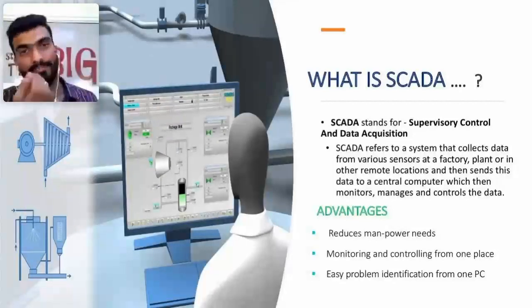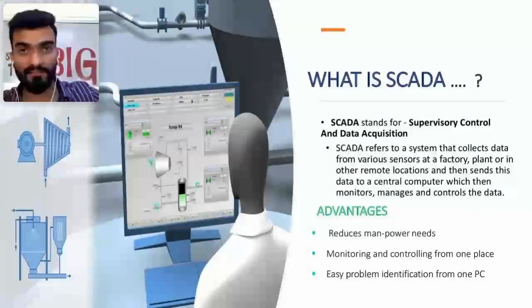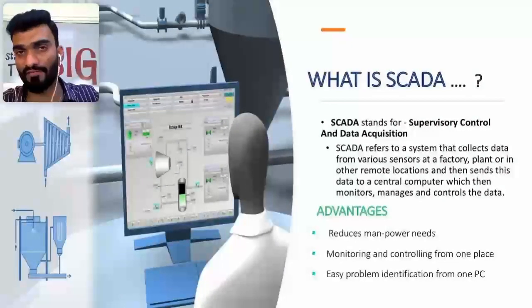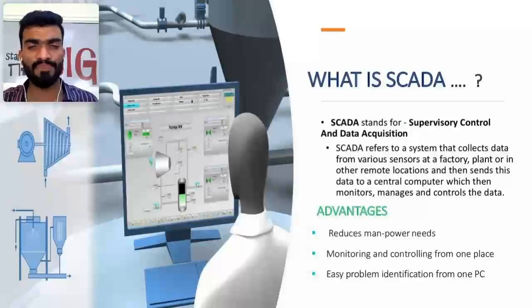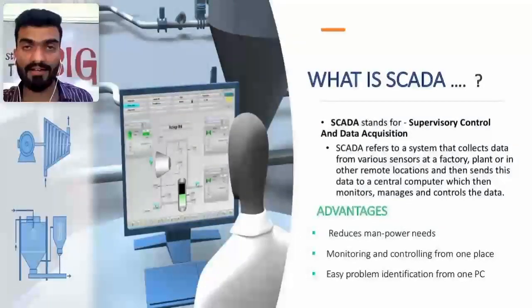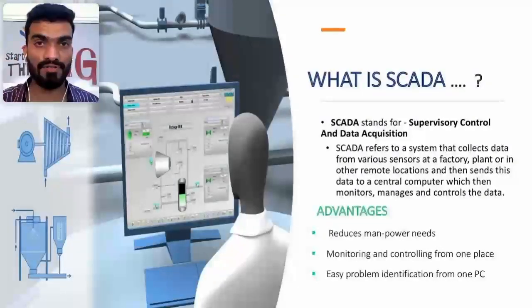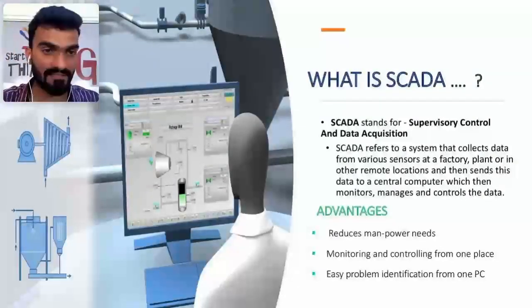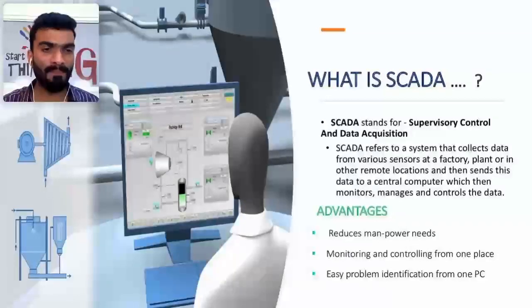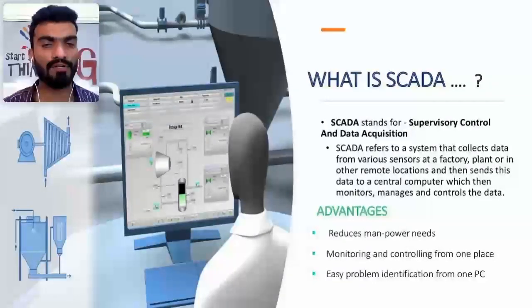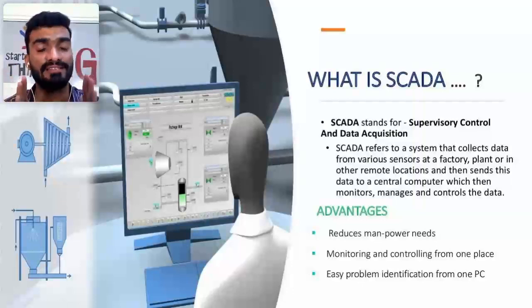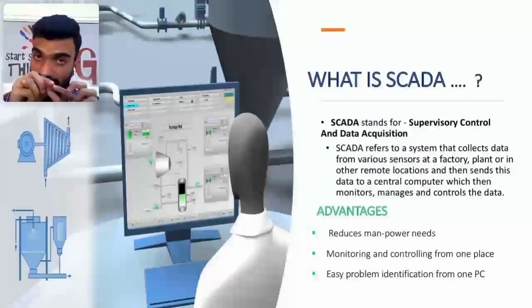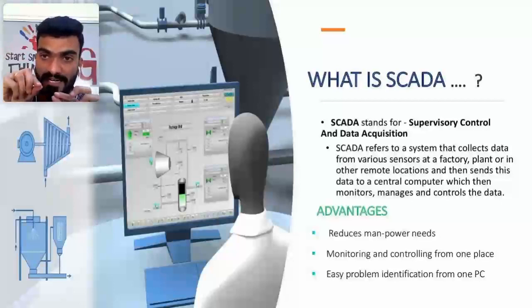When you want to see the previous data of the last 30 days production, or before that, when the machine was started, when it was stopped, what was the production count, what was the breakdown time, everything, you can take all this history back and check. You can generate reports, create trends, create graphics like how we have shown here. We are showing one tank, the level in the tank, and showing turbine, fan, pump, and all. So this is all about SCADA. You can design all these graphics into the SCADA, and give addressing between PLC and SCADA.